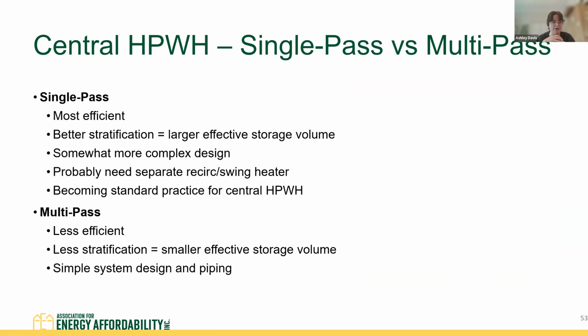And then you have to think about what type of heat pump water heater you're going to choose. They come in single pass or multi-pass configuration. Single pass configuration, exactly what it sounds like. It heats up the water from the incoming cold water temperature to the outlet set point temperature, usually about 140 degrees, in one single pass. These are the most efficient options and create better stratification in your storage tanks. They're a little more complicated. They also do not like to have warm incoming water like your recirculation water. So you probably are going to need some sort of separate recirc or swing type heater. But like I already said, single pass with a swing tank, pretty much standard practice.